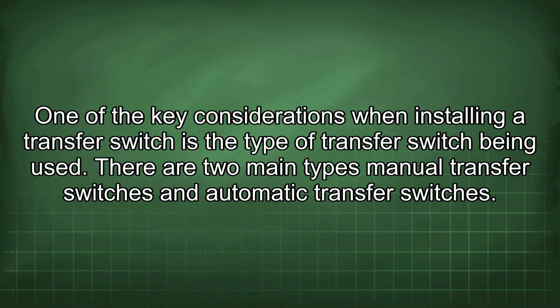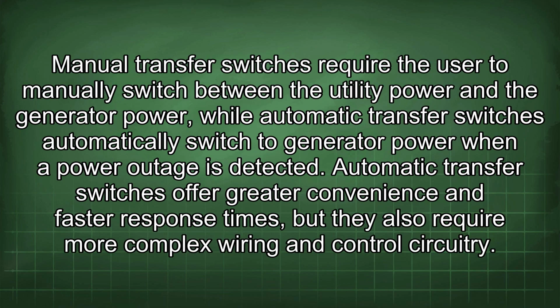One of the key considerations when installing a transfer switch is the type of transfer switch being used. There are two main types: manual transfer switches and automatic transfer switches. Manual transfer switches require the user to manually switch between the utility power and the generator power, while automatic transfer switches automatically switch to generator power when a power outage is detected. Automatic transfer switches offer greater convenience and faster response times, but they also require more complex wiring and control circuitry.